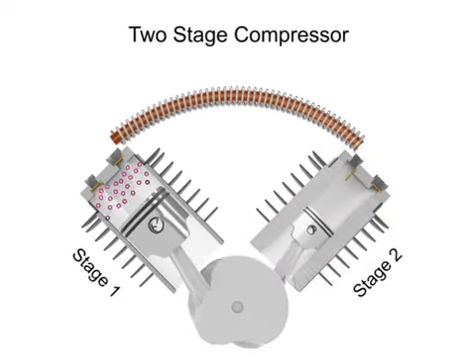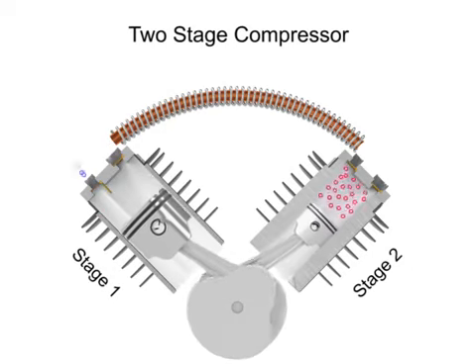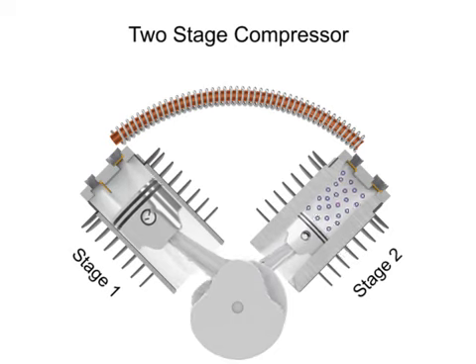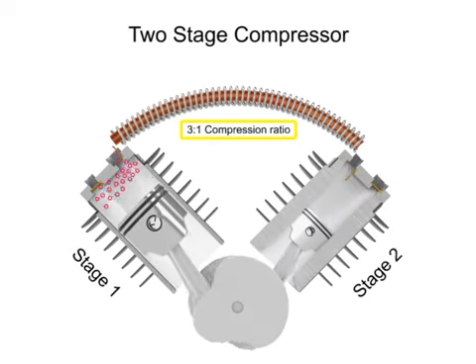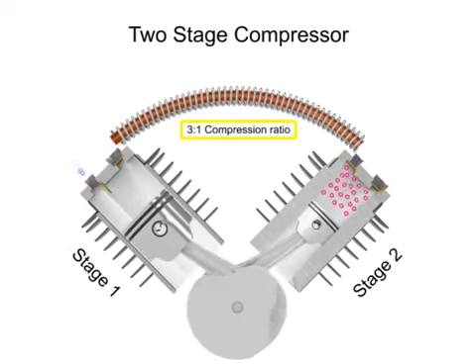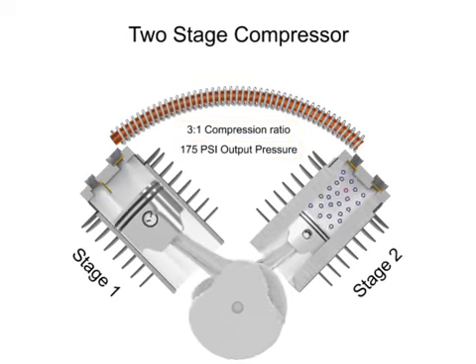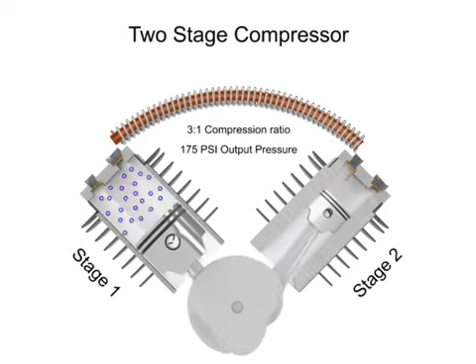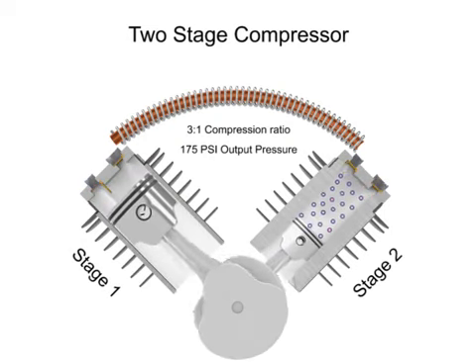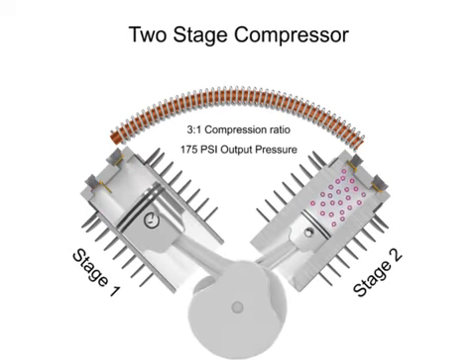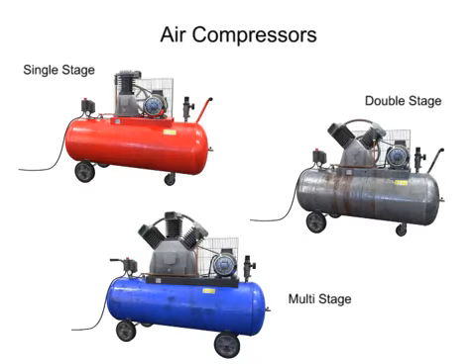The compressed air entering the second stage is sometimes called supercharged air. Two-stage compressors have a compression range of 3 to 1 or even less per stage, but can operate up to 175 PSI. They can also deliver more air at a higher pressure than single-stage compressors of the same horsepower. If pressures of more than about 175 PSI are needed, multi-stage compressors should be used.